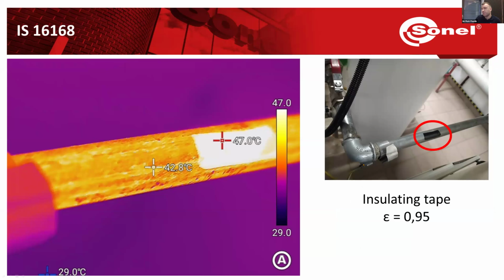Here you have an example. I'm checking some sort of a pipe. Now the pipe is made of metal, so it has rather low emissivity. Metals work like a mirror for the infrared radiation, and therefore the temperature reading will be higher. So what can we do? I can put the insulation tape on the pipe, like here, or on my object. I can set the emissivity on the camera to 0.95 and measure the temperature on this piece of tape. Here you can see 47 degrees Celsius.